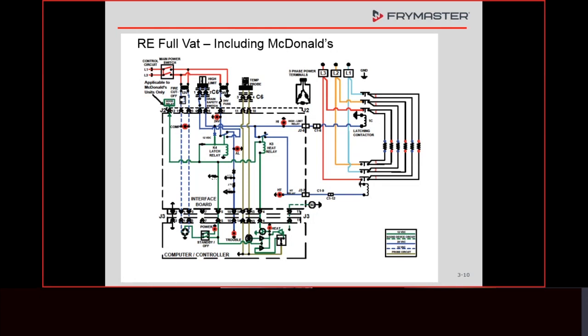Because when we press the button on the controller, it automatically pulls this in, anticipating the fact that we're going to drop temperature because we're about to put product in there. So we push the button, this contactor pulls in, then we're going to start heating. This contactor stays pulled in as soon as you turn the fryer on. When we get voltage to the coil of the latch relay, the 24 volts AC comes in, goes through the relay on the interface board. It goes out pin number 6, goes through the drain switch, goes through the high limit, comes back on pin number 9.